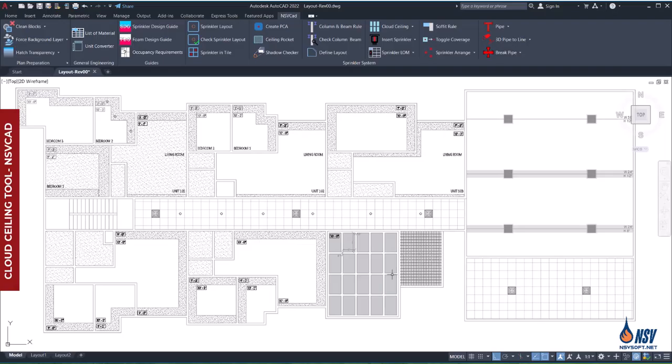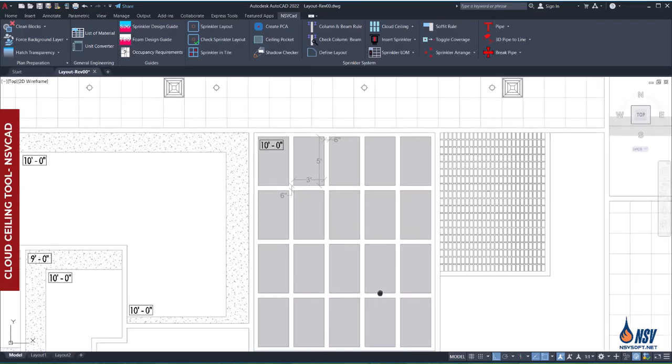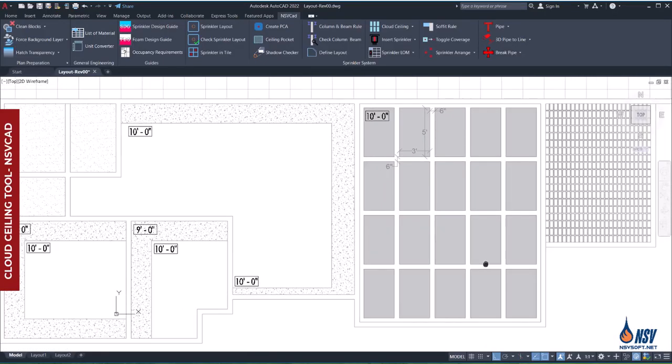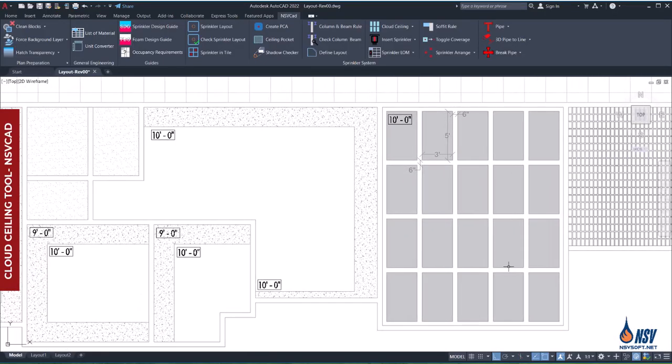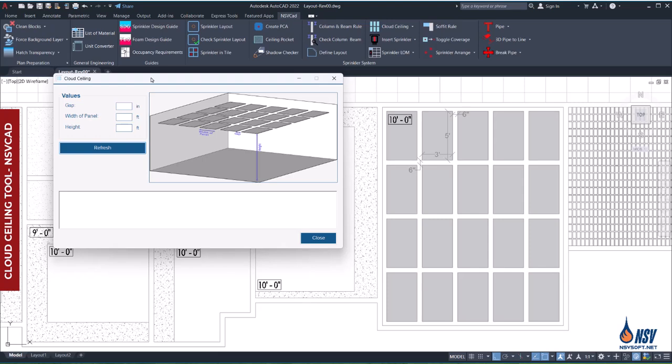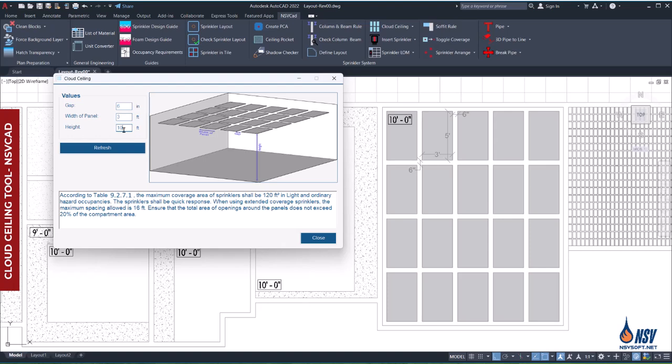In this section, we'll use the cloud ceiling tool in NSV CAD software to identify the requirements for proper sprinkler placement. The layout includes all relevant dimensions clearly marked for reference. When we run the application, a window appears prompting us to enter three key values: the gap width, the minimum dimension of the ceiling panel, and the ceiling height. Once these are entered, the software calculates and displays the relevant NFPA 13 requirements based on the input.